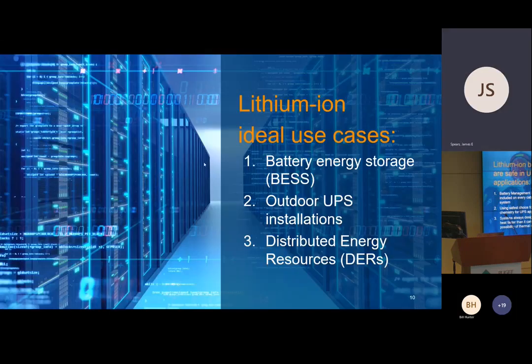Ideal use cases include UPSs, but also battery energy storage, or BESS, which could be indoor or outdoor. Typically we're talking about longer backup time, 1 to 4 hours or more, used strictly as an energy storage application. When they get that big, they need to be deployed outdoors as well as indoors, which means they need climate control arrangements just like if the battery were indoors, regardless of the weather outside.